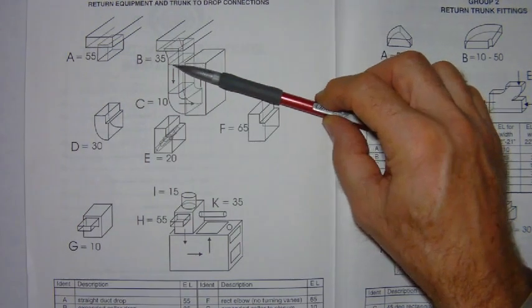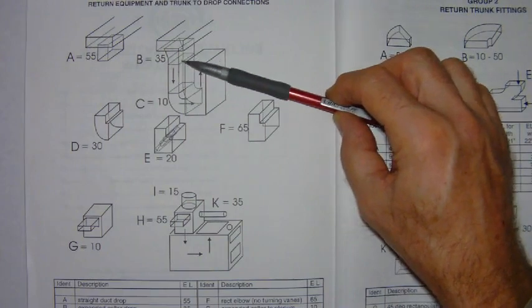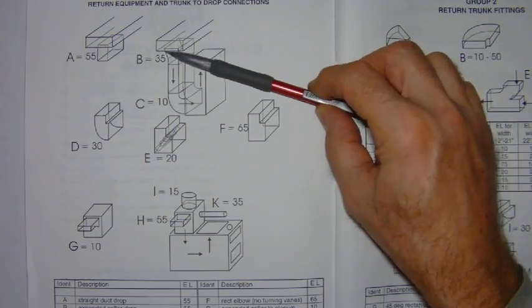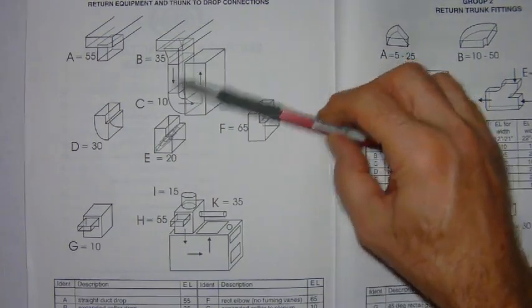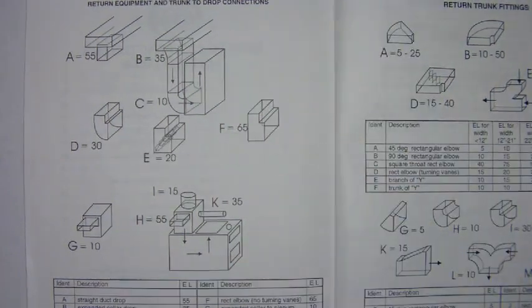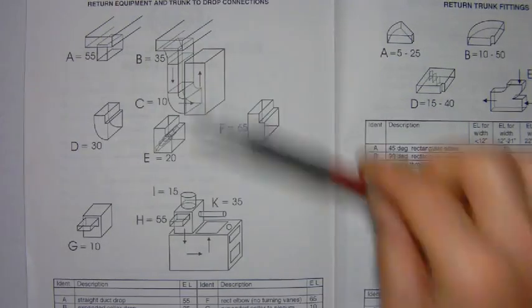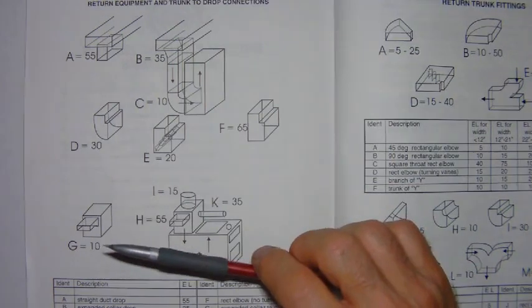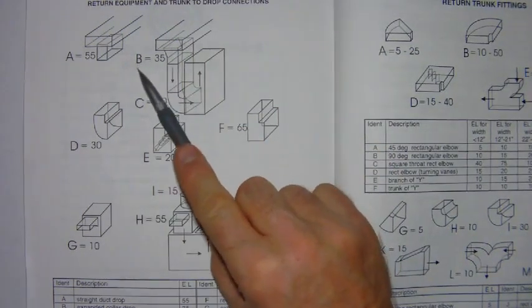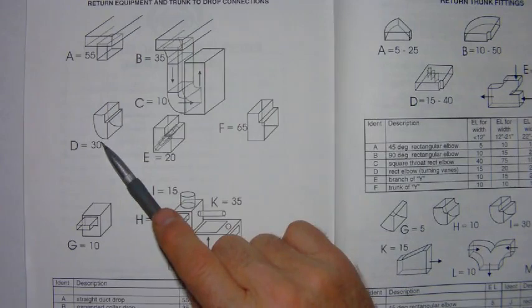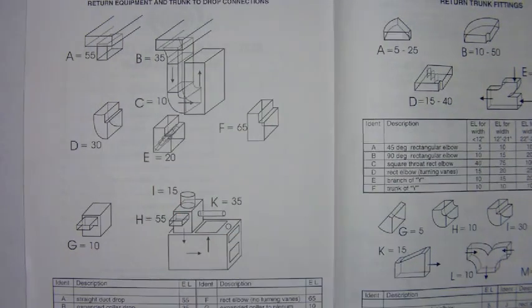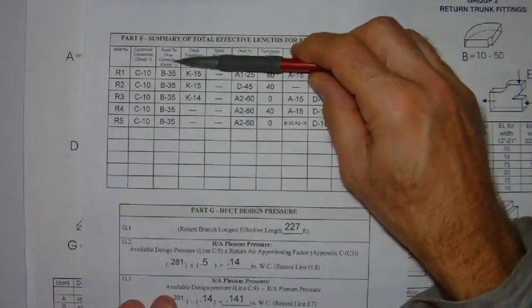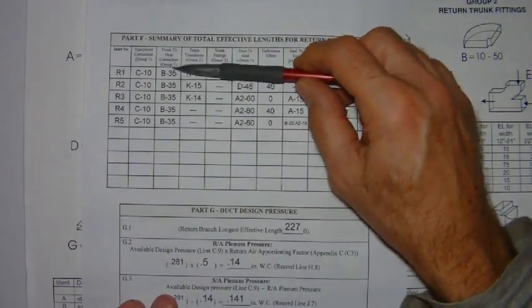And this B fitting is referred to as an expanded collar and you can see it looks a bit like a funnel. It's got a larger area connecting to the duct and it transitions down to the smaller duct size. It simply helps to convey the air from the trunk down into the return drop more effectively. And so that's a B fitting and it's got 35 feet of equivalent length. And so that is our trunk to drop connection B35.